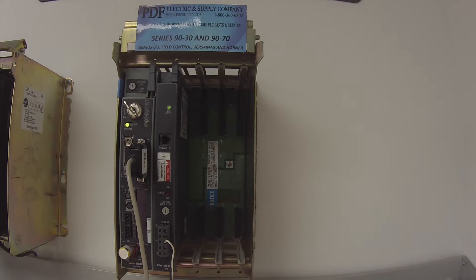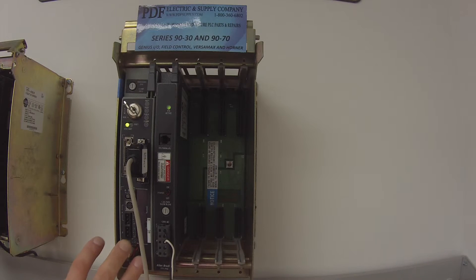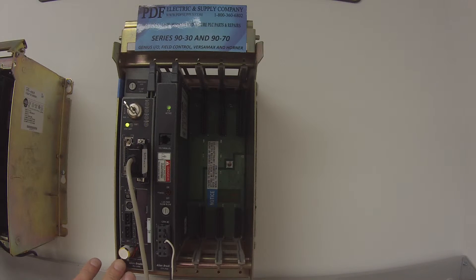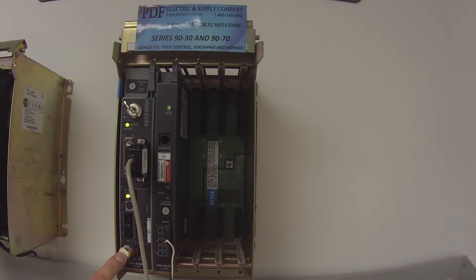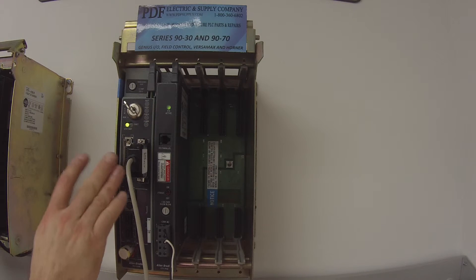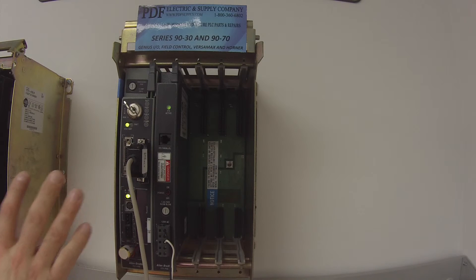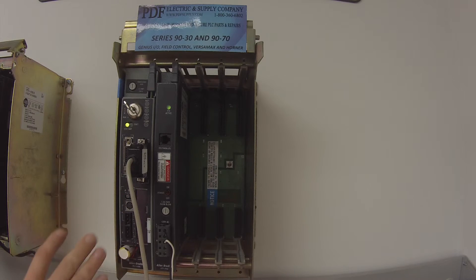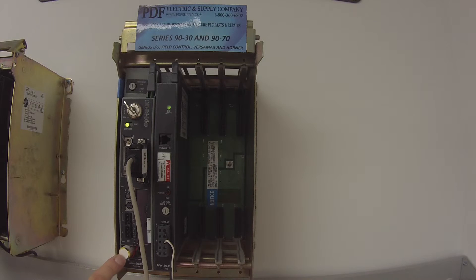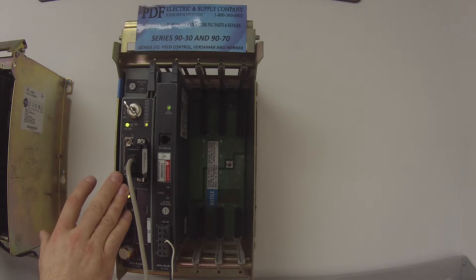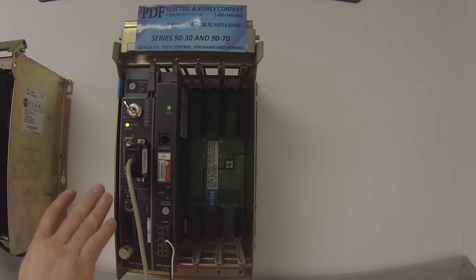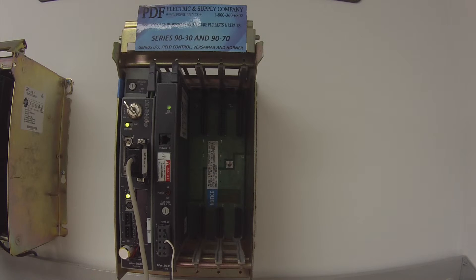Another little bit of information is, as you can see, a lot of my test units, I don't always use a battery. In this particular case, I recommend that you do use a battery because if and when you do change the ethernet address, it may ask you to power cycle. So you want to make sure that you're backed up with a battery that's going to hold that IP address in there while you power cycle. So always have a battery when you're testing the ethernet module.